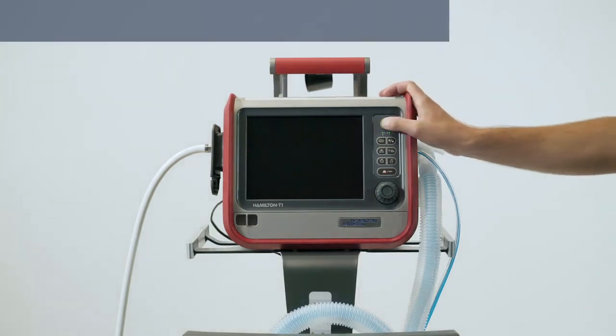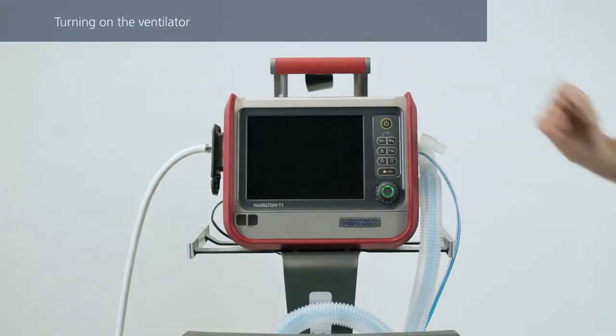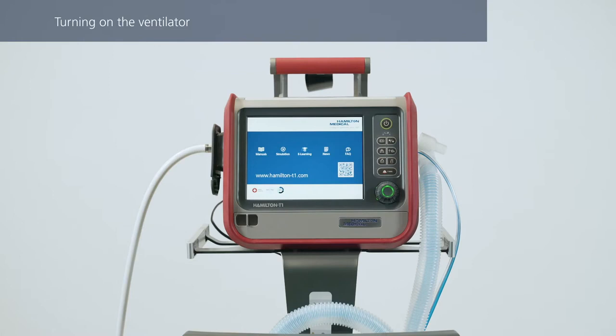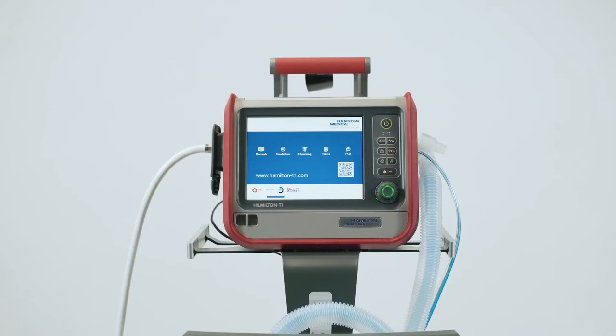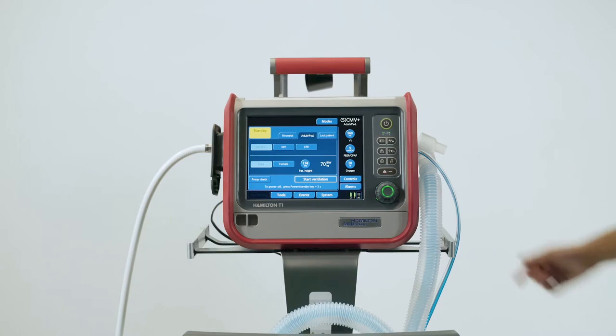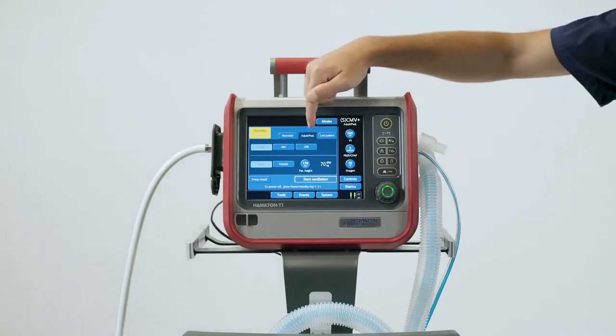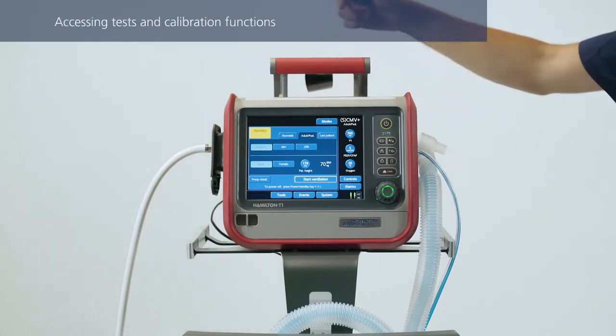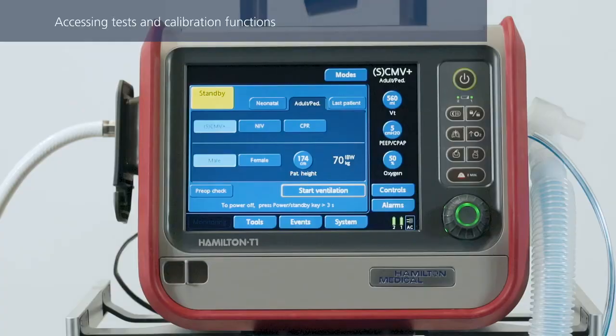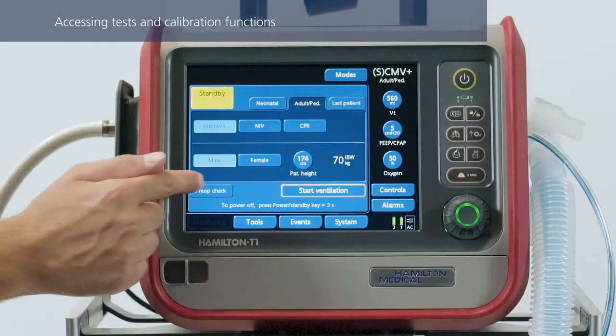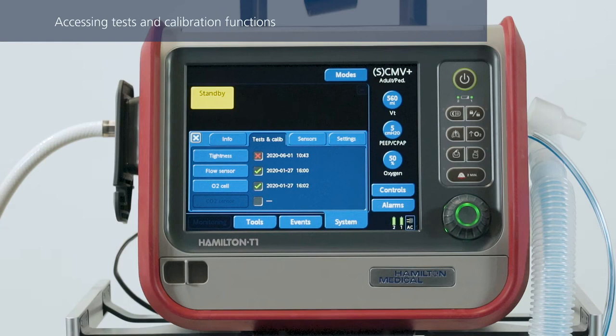Press the power standby key to turn on the ventilator. The ventilator will automatically run a self-test. Once that's finished, you can go ahead and select the correct patient group. To access the tests and calibration functions, touch Pre-op Check in the standby window. The Tests and Calib window opens.